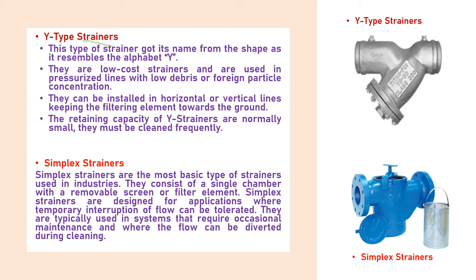Y-type strainers are called Y-type because when mounted, they form a horizontal Y shape. These are low-cost strainers used in pressurized lines with low debris or foreign particle concentration. For example, in pump systems, Y-type strainers are commonly used. They can be installed in horizontal or vertical lines, with the filtering element kept towards the ground, giving flexibility in installation.